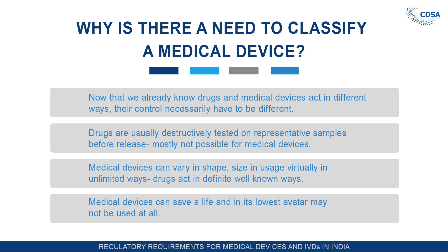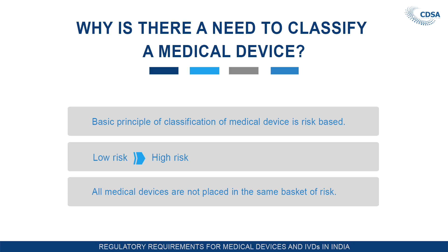The basic principle of classification of medical devices is risk-based. We knew earlier, low risk to high risk. Lowest risk medical devices are simple items like a walking stick, spectacles, a hospital bed or a bedpan. And the high risk, of course, can be IVDs for HIV, cardiac stents and brain implants. All medical devices are not placed in the same basket of risk. Over here, may I mention that the classification of a medical device is dependent on its usage. The same medical device can be used in a high risk class also and a low risk class also.